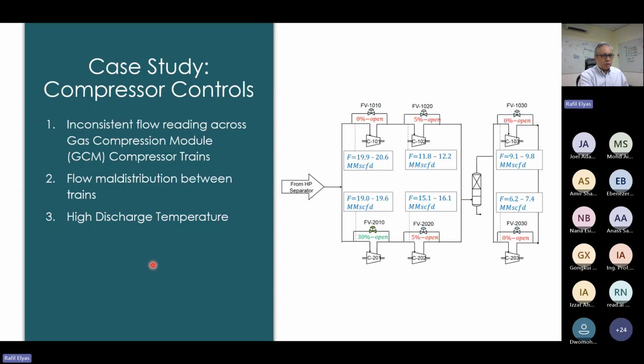And one of the compressors was having a high discharge temperature at this point over here. The expected discharge temperature should have been about 140 or so, but we were getting up to about 170, 180. And at the suction header, even at a low gas throughput, we're getting a lot of flaring taking place.